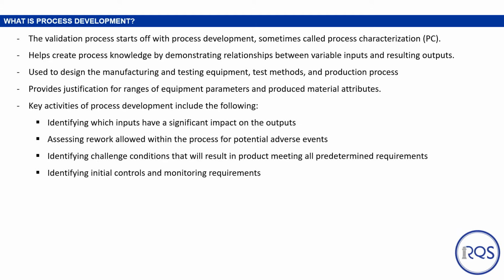The validation process starts off with process development, sometimes called process characterization or PC. Process development helps to create process knowledge by demonstrating relationships between inputs and outputs. Process validation is used to design the manufacturing and testing equipment, test methods, and production processes to support the manufacturing and testing of a product. Process development also provides justification for ranges of equipment parameters and produced material attributes. Key activities in process development include identifying which inputs have significant impact on the outputs, assessing rework allowed within the process for potential adverse events, identifying challenge conditions that will result in product meeting all predetermined requirements, and identifying initial controls and monitoring requirements. We will walk through each of these in more detail now.